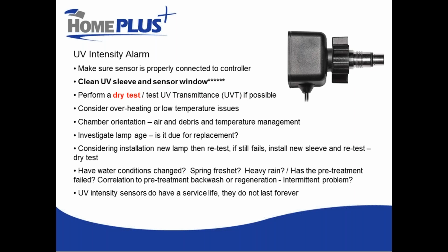If you have a newer lamp, I would probably suspect that it is not that and move on deeper into troubleshooting, because we don't want to just replace the lamp, bump the UV intensity a few percent, narrowly get out of an alarm condition and just set ourselves up to have another alarm in the near future. The next thing you should do, and this should be a part of your regular maintenance anyway, is clean the UV sleeve.